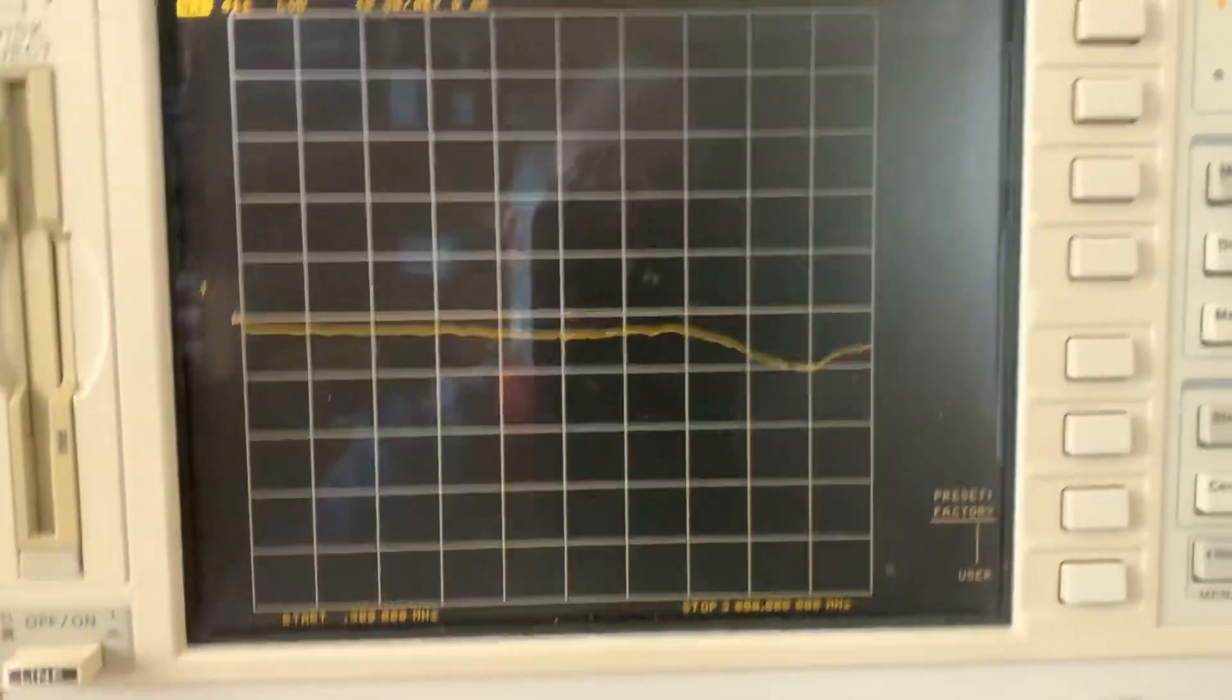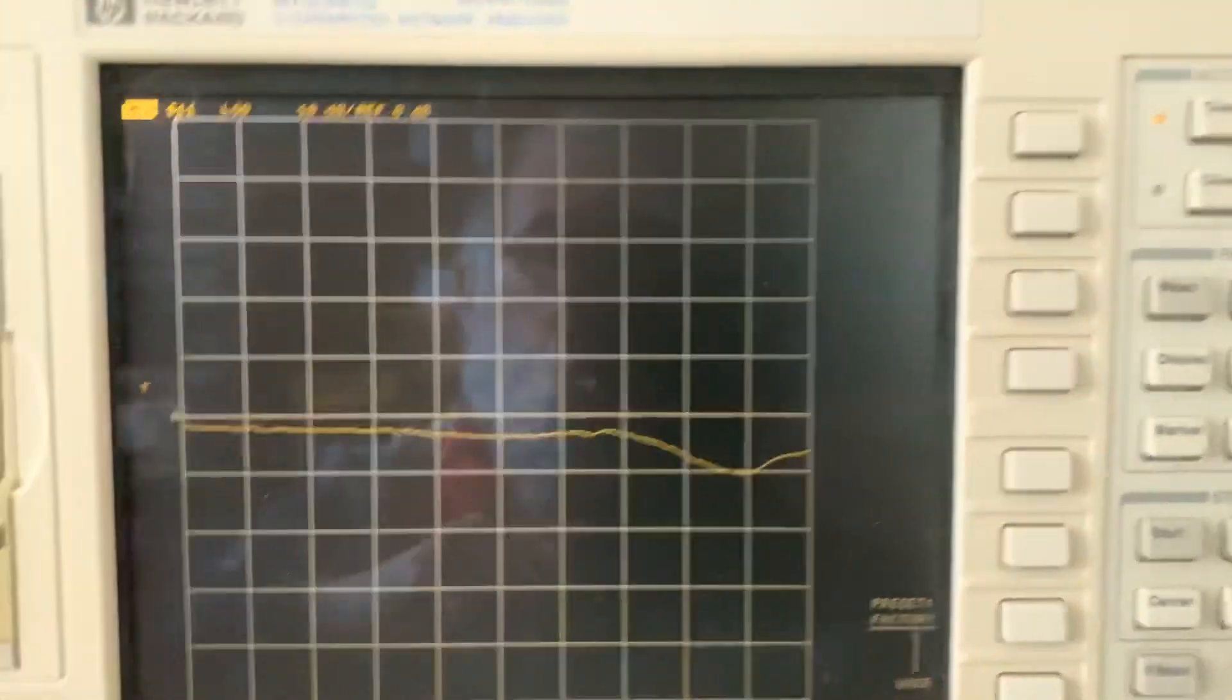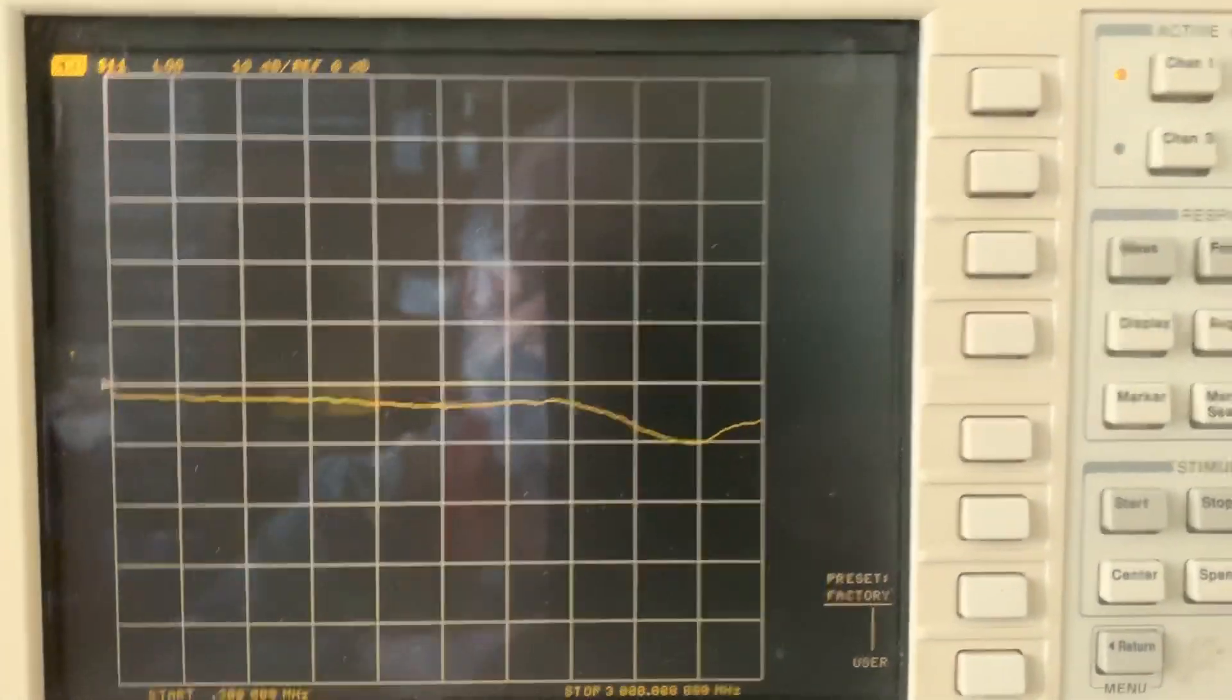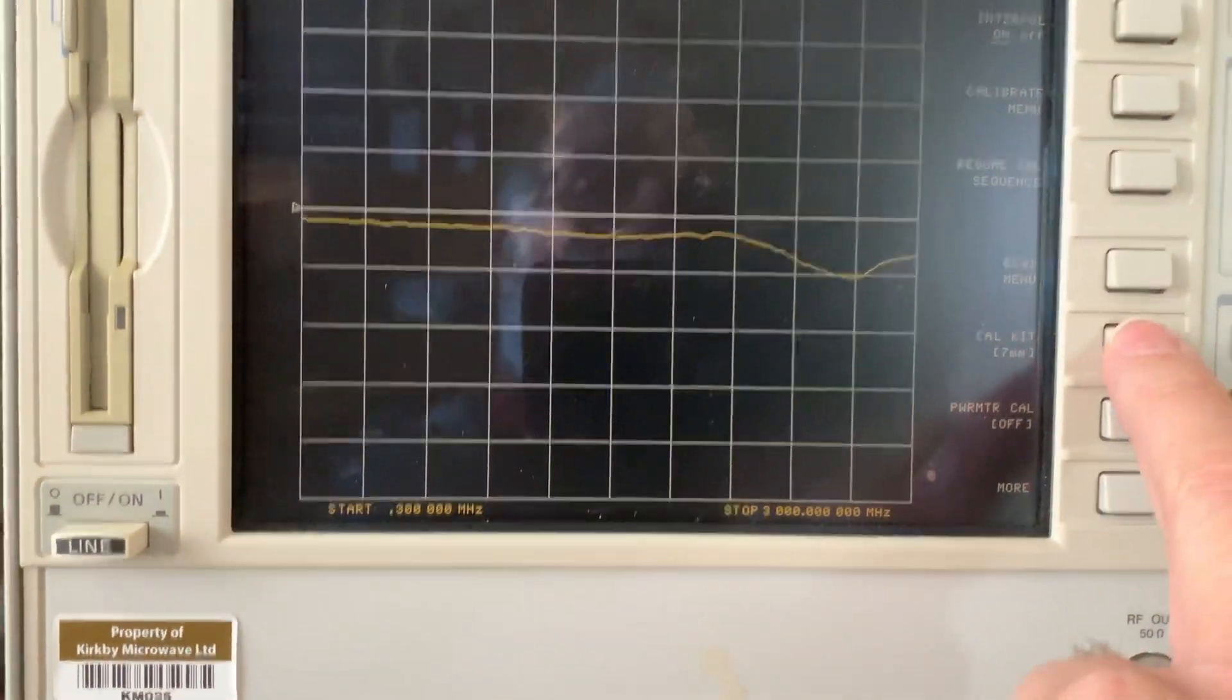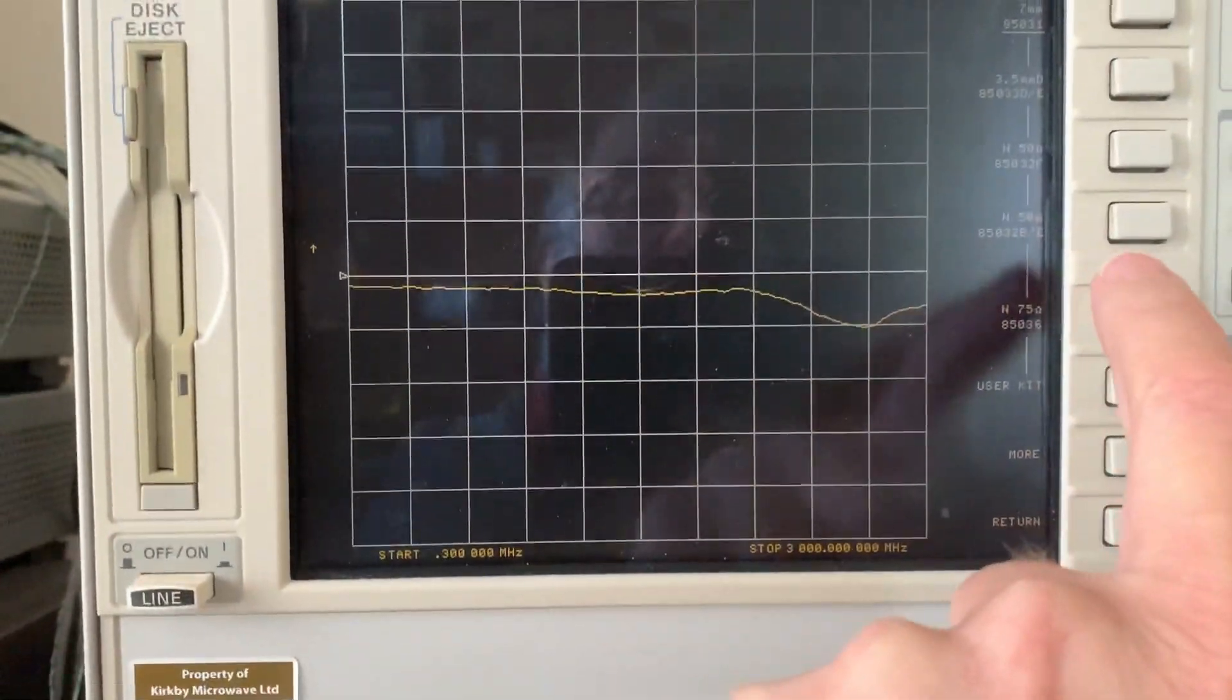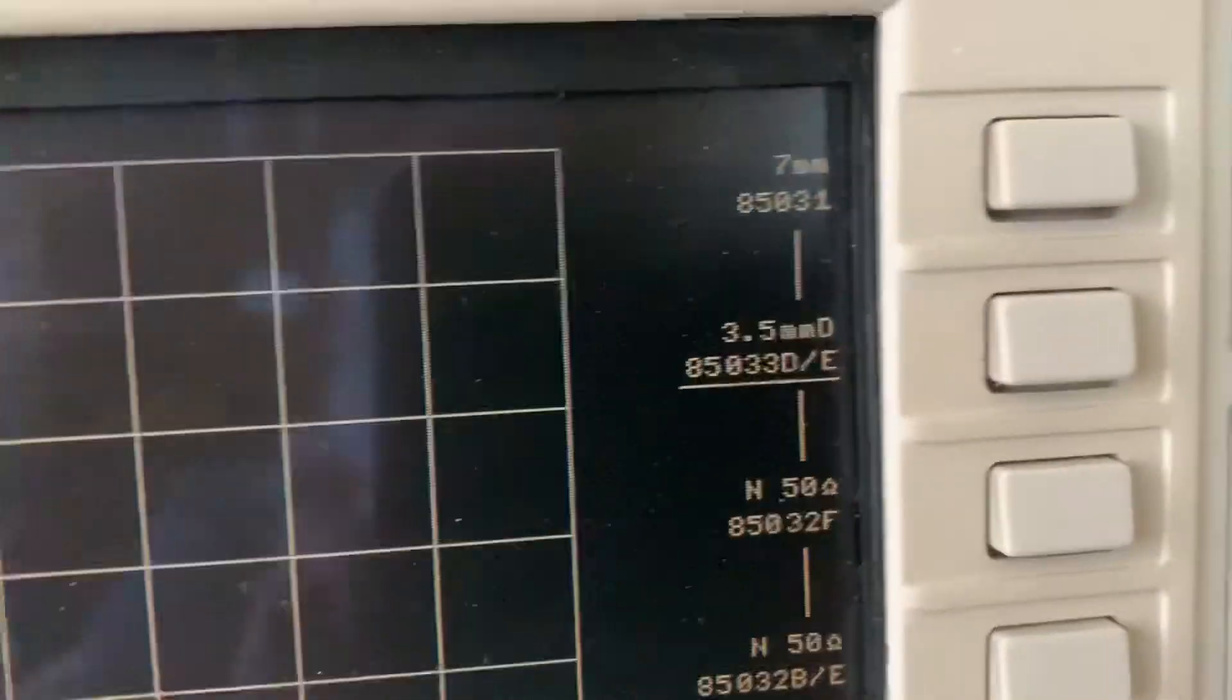I'm going to select a 3.5mm calibration kit as that's the nearest we've got to an SMA. Cal kit, select cal kit, 3.5 millimeters. That's 3.5 millimeters.